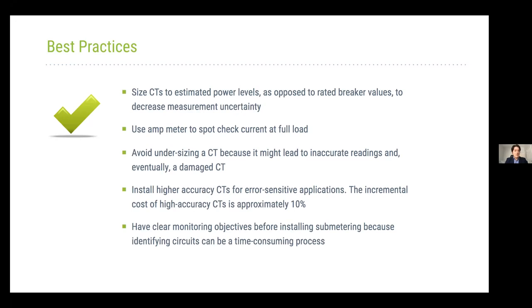Once we identify the end use case, whether it's FTD or tenant billing where we might need high accuracy, that gives a better idea of what equipment is required. For high accuracy applications, installing high accuracy CTs for error-sensitive applications is the best route, especially since the incremental cost is only approximately 10% more.